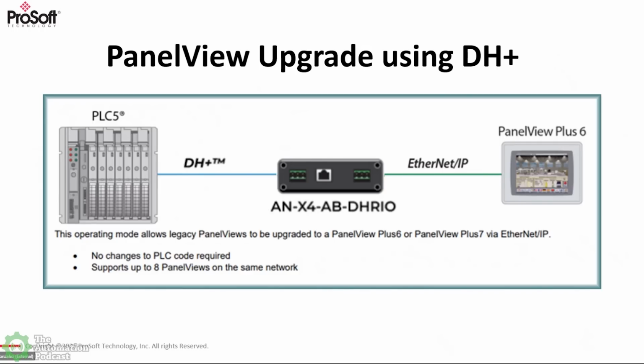This one supports up to 8 panel views on the same network. So let's say all you can get is a panel view plus 7, and all that has is Ethernet. But your old panel view was talking DH Plus to your PLC5, like the 504s. So now we're using the same AN-X4 in reverse, where it's not the PC talking through Ethernet, but the panel view talking through Ethernet to the Data Highway Plus network. That's great for situations where people can only get the panel view plus 7, which has no DH Plus option.